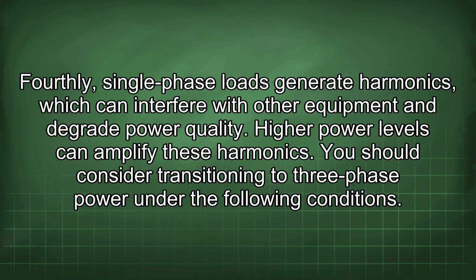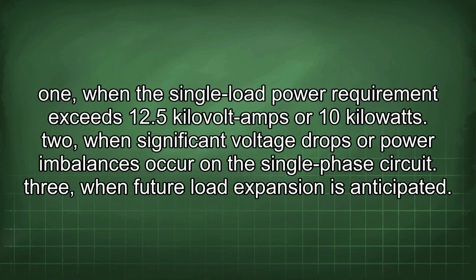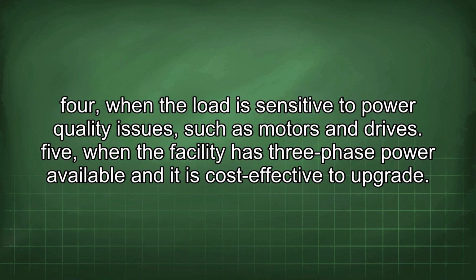You should consider transitioning to three-phase power under the following conditions. 1. When the single load power requirement exceeds 12.5 kilovolt-amps or 10 kilowatts. 2. When significant voltage drops or power imbalances occur on the single-phase circuit. 3. When future load expansion is anticipated. 4. When the load is sensitive to power quality issues, such as motors and drives. 5. When the facility has three-phase power available and it is cost-effective to upgrade.